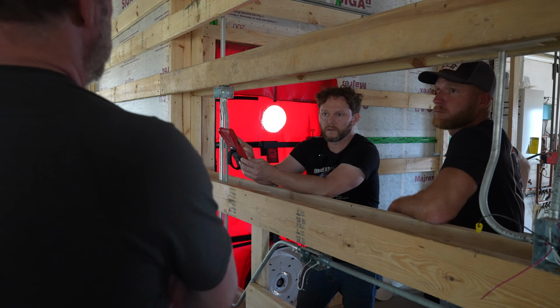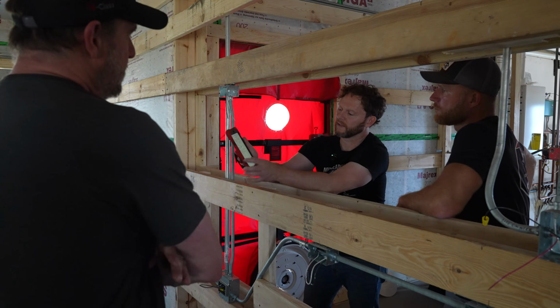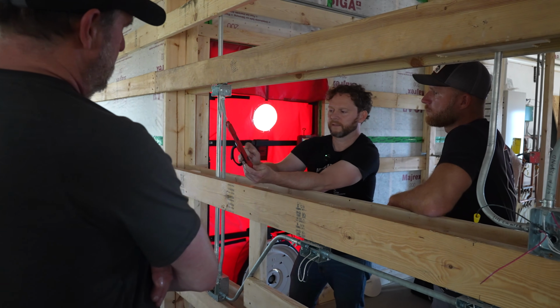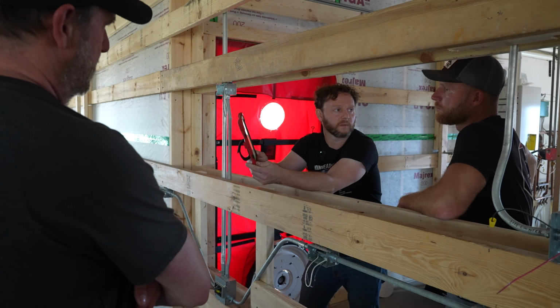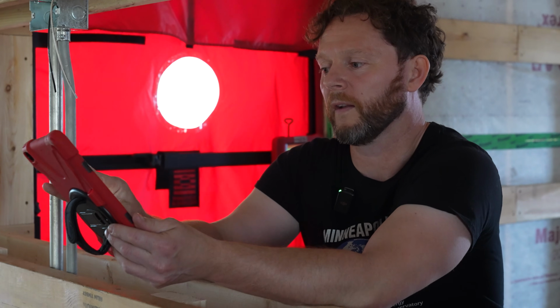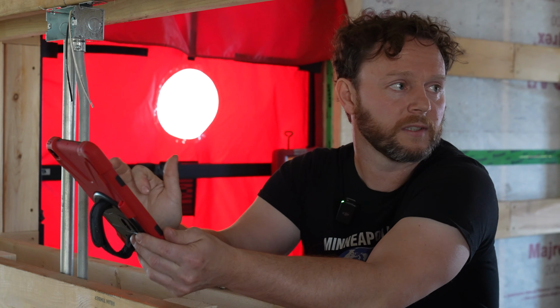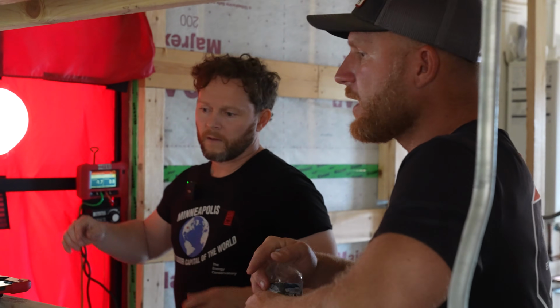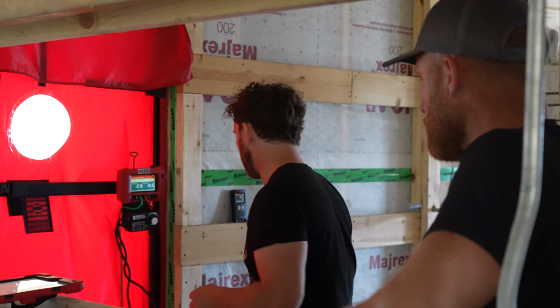Okay. So I'd like a little bit higher. What that's saying is how close all these points fit on that line. That one right there is a little bit higher, that one's a little bit lower. That's why I'd want to redo that, because we had some wind. We're fighting with wind, and that is potentially going to change that a little bit. So let's pressurize it, find some leaks, hopefully, and then we can run it again. Yep, let's do it.